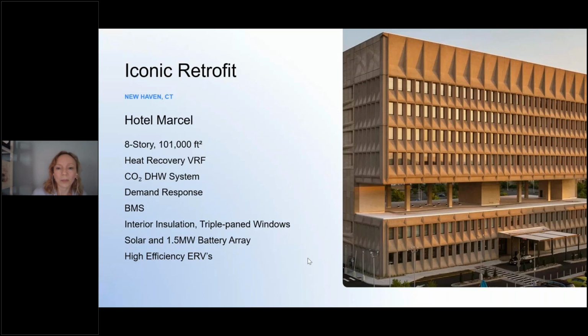I won't talk about those as much as the two elements that set this project apart, which are the CO2, the carbon dioxide refrigerant based domestic hot water system that's being used for all of the laundry, hot water, and cooking for the hotel, as well as the demand response system that's been integrated into the BMS.